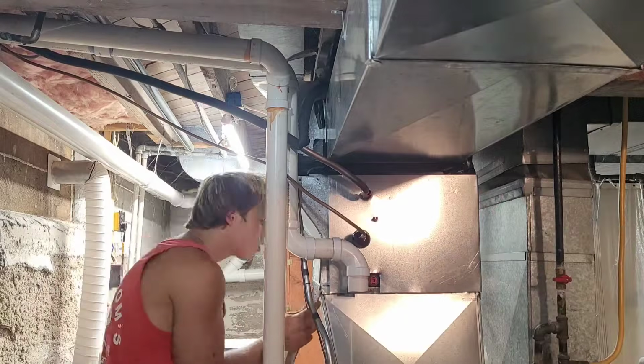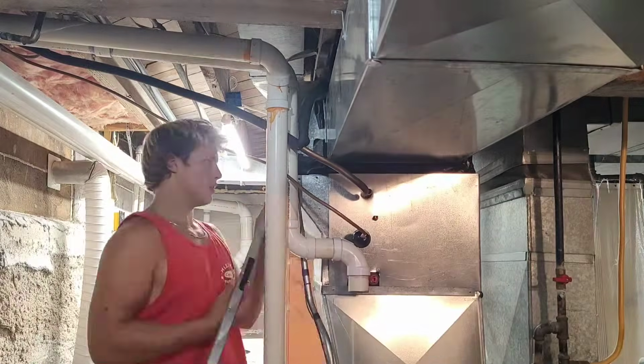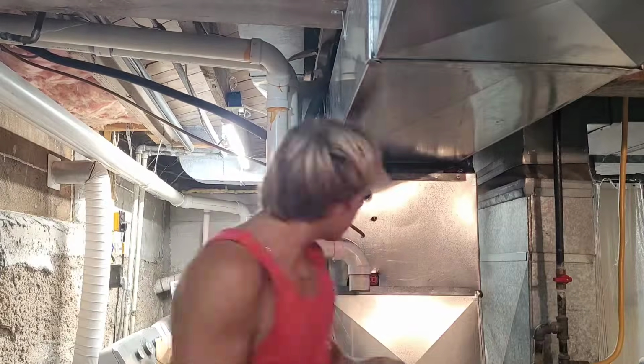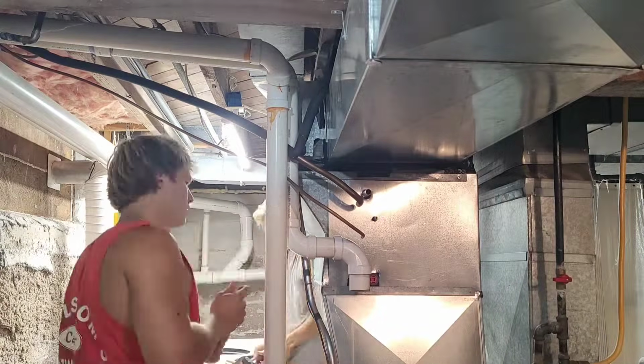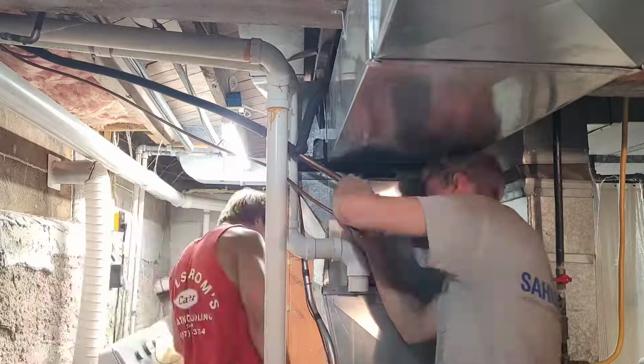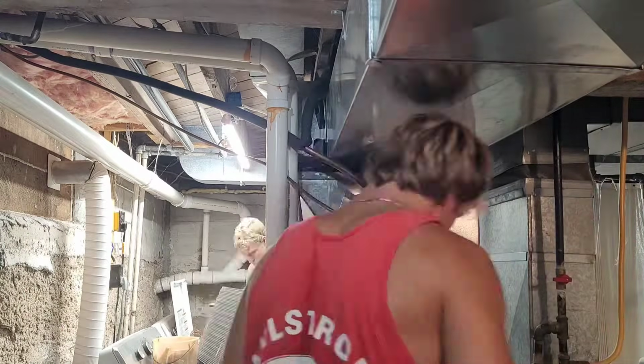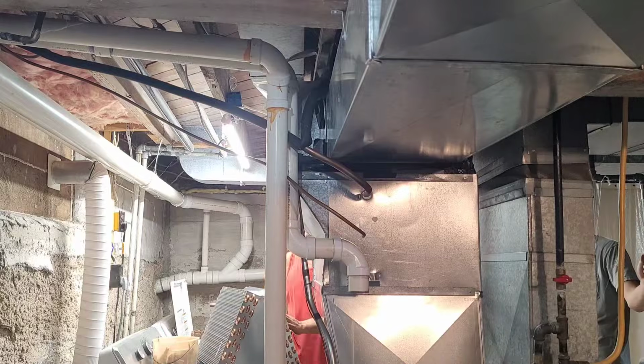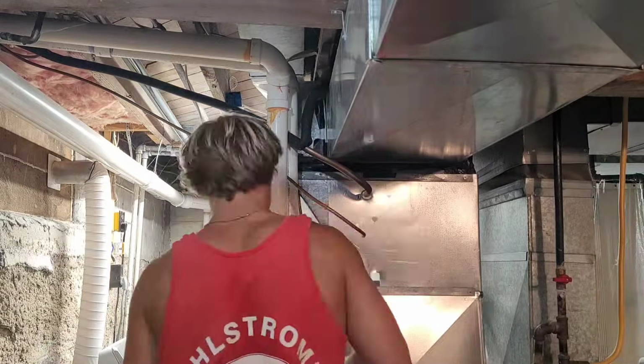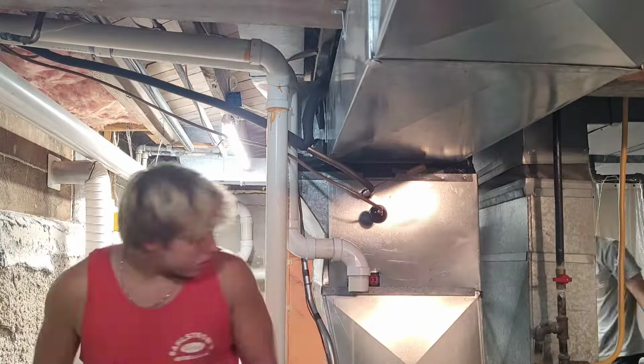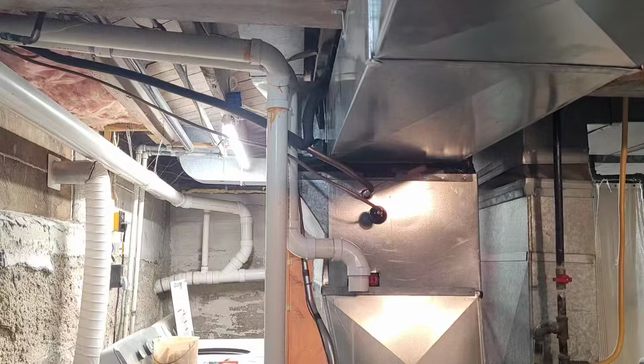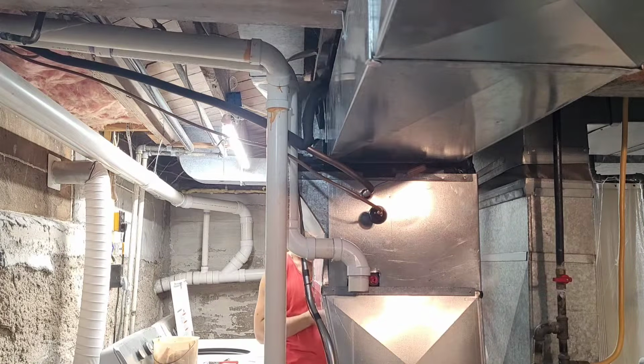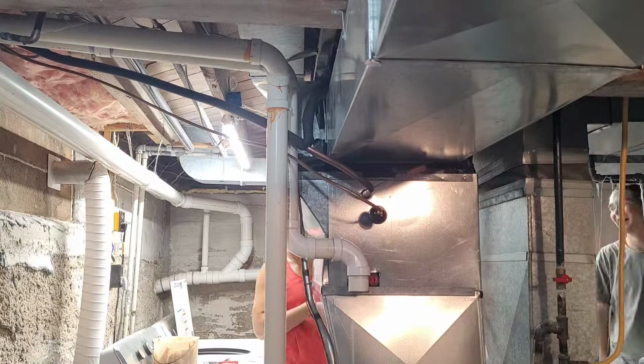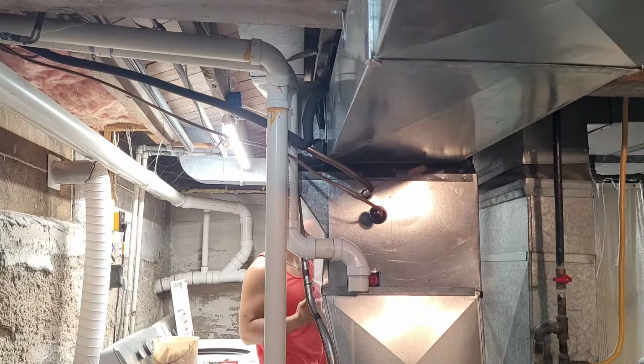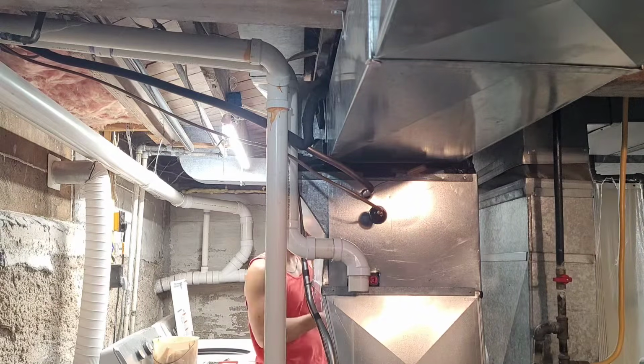I decided to put the filter dryer on the inside liquid line right before it goes into the coil and expansion valve. Just seems like some places it works better to put it inside, some places it works better to put it outside, but the closer you can get it to the orifice or expansion valve, the better it protects it, in my opinion. Sort of seems like installing the outdoor unit would be more time consuming, but I've found that putting the coil in is usually what takes the most time, just because the ductwork is always different and it just takes a while to get it put in such a way that it looks nice and works well.